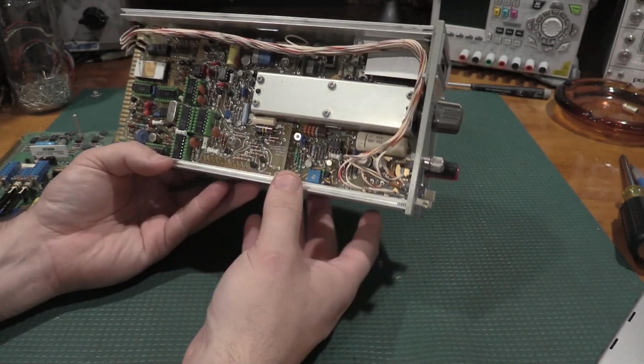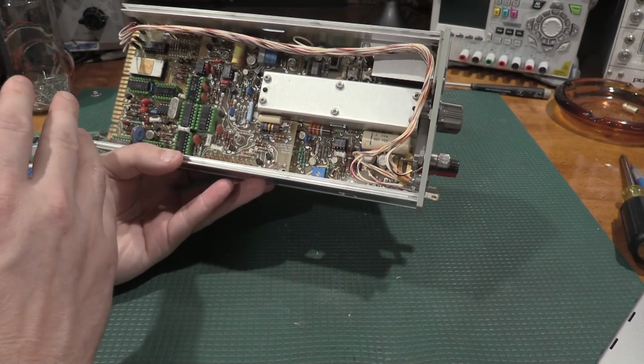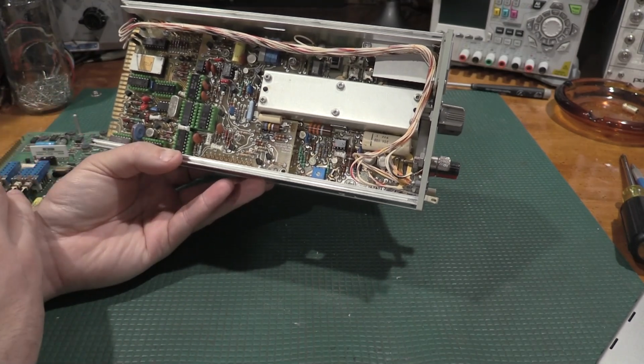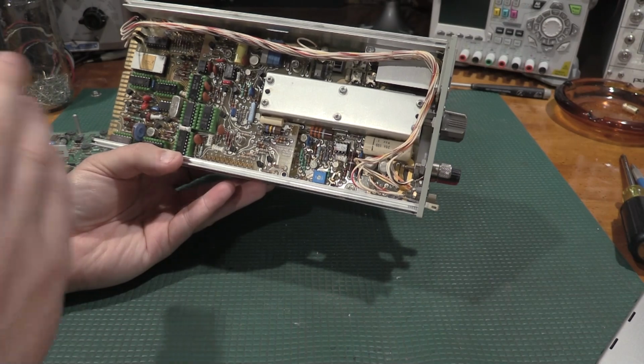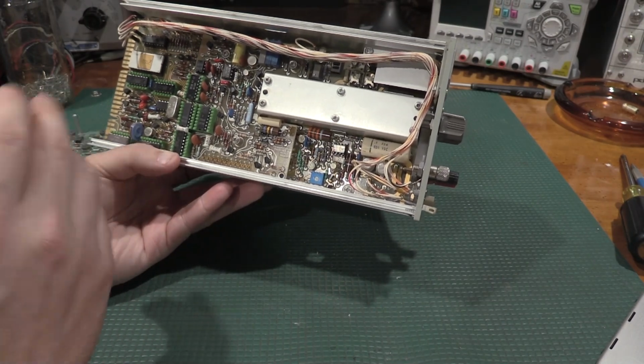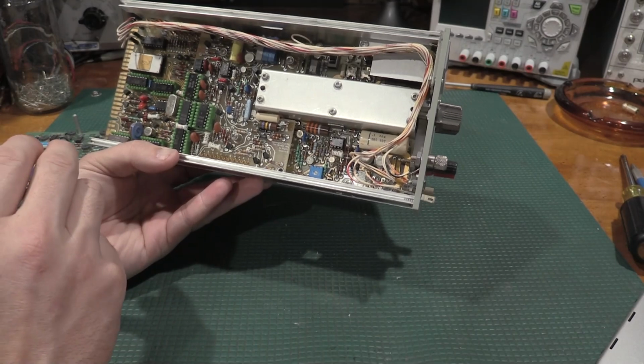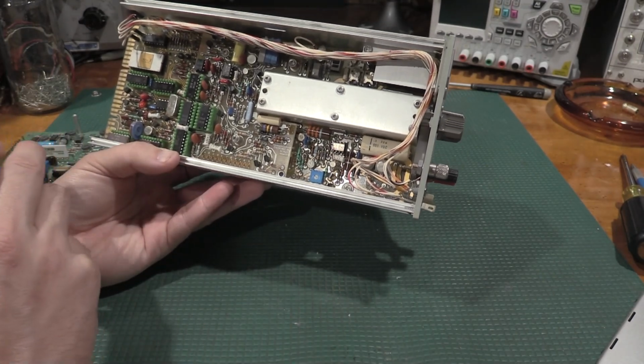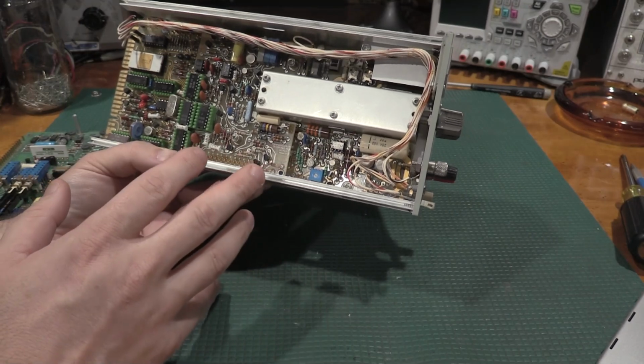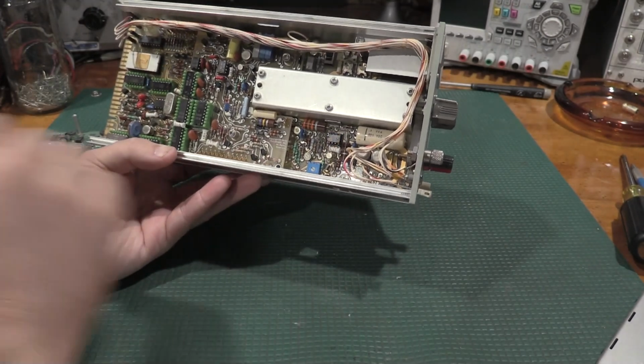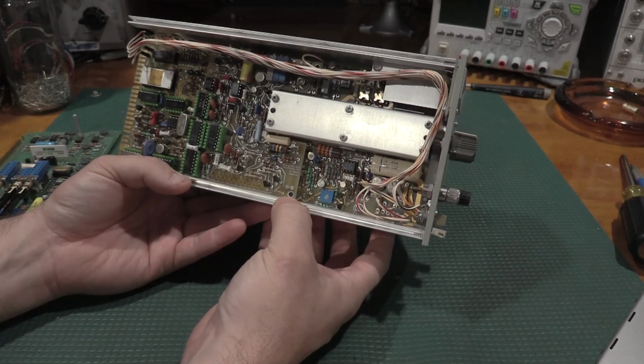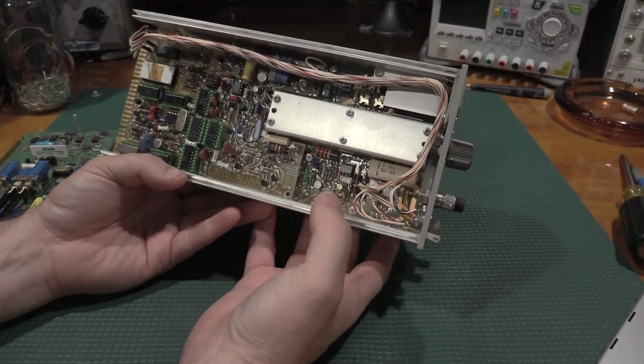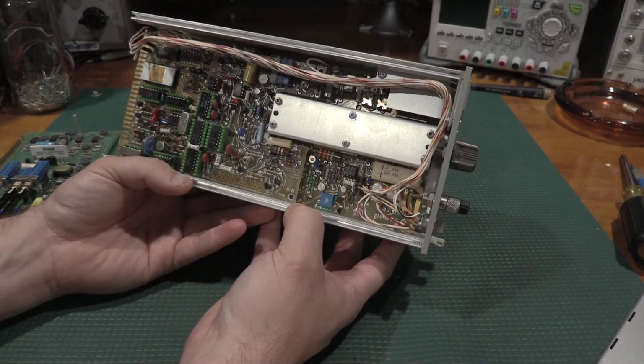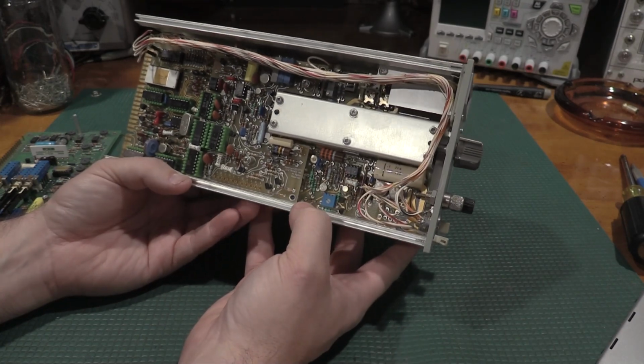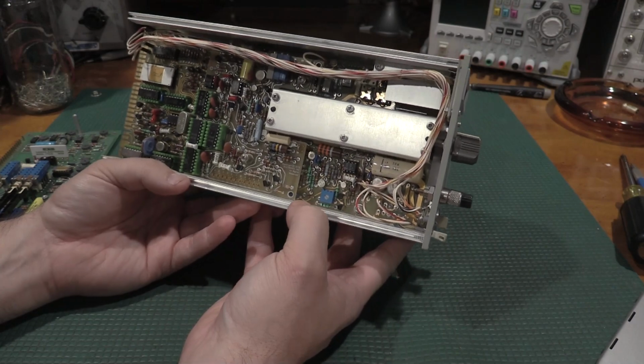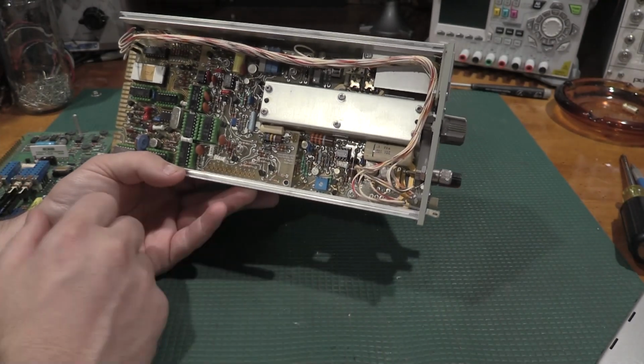So what happens with a lot of this equipment is when they're brand new, the components are still getting burned in, things like that. References are aging, things like that. In high-end meters, like my 7500, my 7.5 digit, the references are burned in before they even see a unit. So they have a whole bunch of parts. They're baking those in, sometimes for a year or more. But they have a procedure that they know works to stabilize them. But as the units age, they actually become more and more stable. So eventually you end up just checking in the equipment.